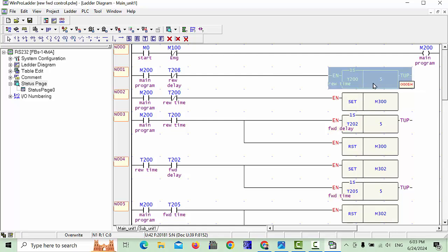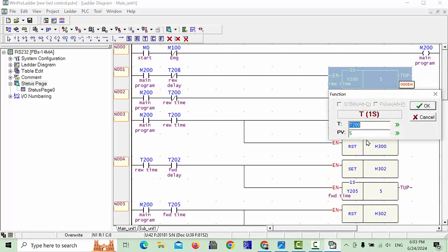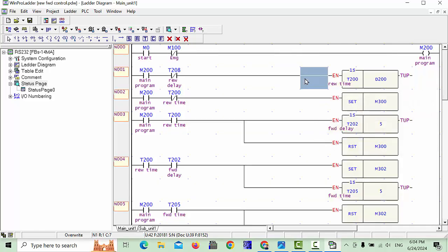You click on this one, and here you write T200 — this is your timer address. And here you give the value. The reason is: when you are using it in the program, if you can't give that value every time — opening with a laptop or whatever, having to change the value every time — sometimes you have to take the data register. For example, I will take D200 here. Give the same name: T200, and I give D200. This D200 value you will take from the HMI, and whichever value you write — for example 200 — that value will be counted in this T200 memory. Click OK and now your timer is ready with data registers.